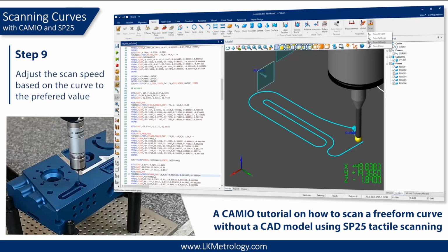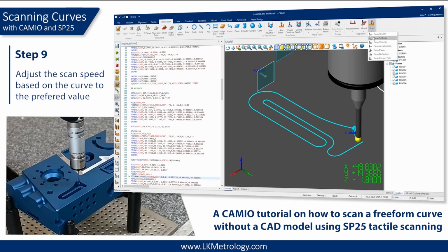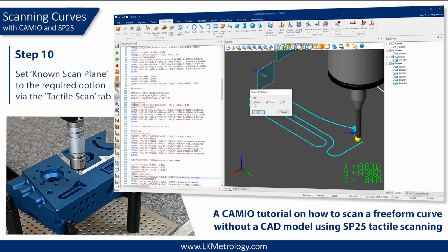We can set our scan speed based on the complexity of the curve we are scanning. This is done using the Scan Velocity option available in the Scan Settings drop-down list. To keep the probe in the same plane, set the known scan plane from the known path scan option in the same drop-down list from the Tactile Scan tab.